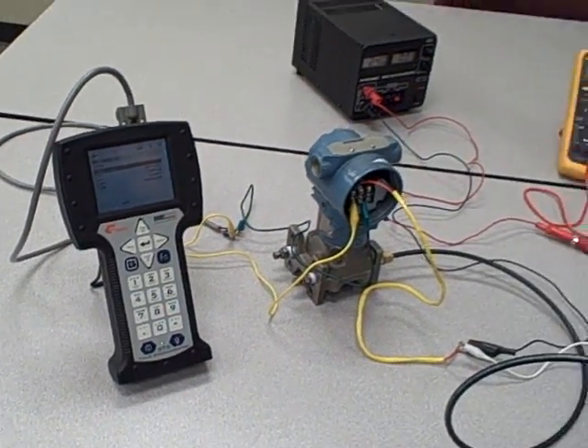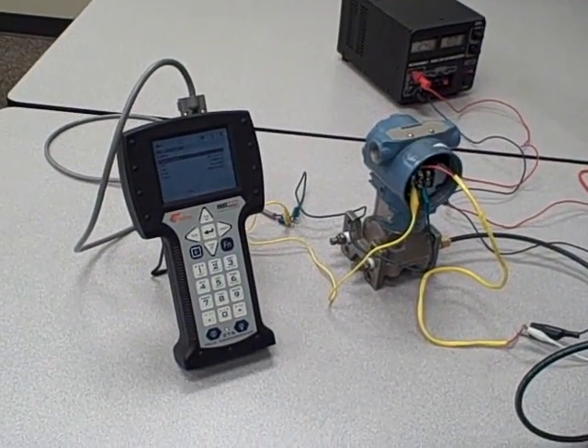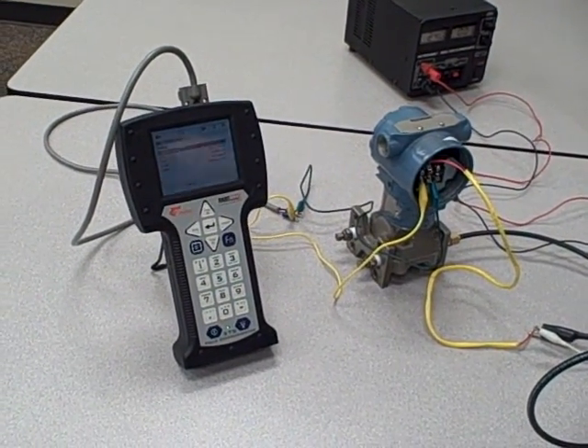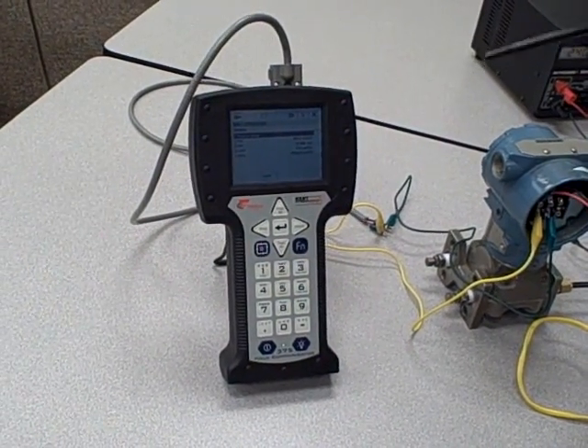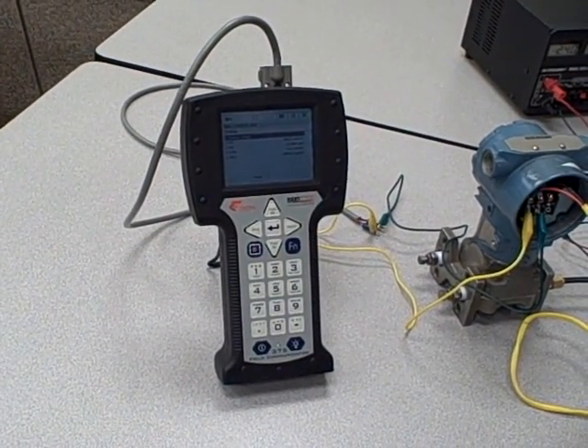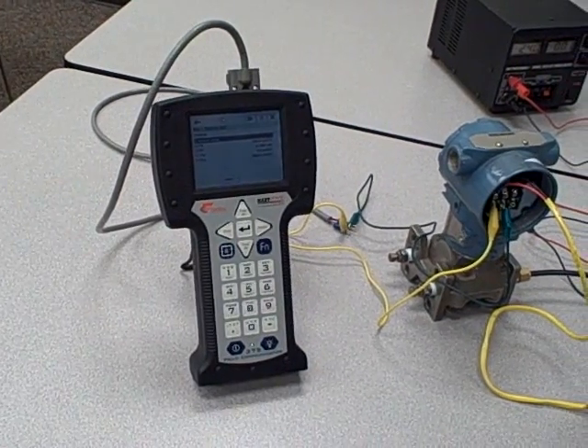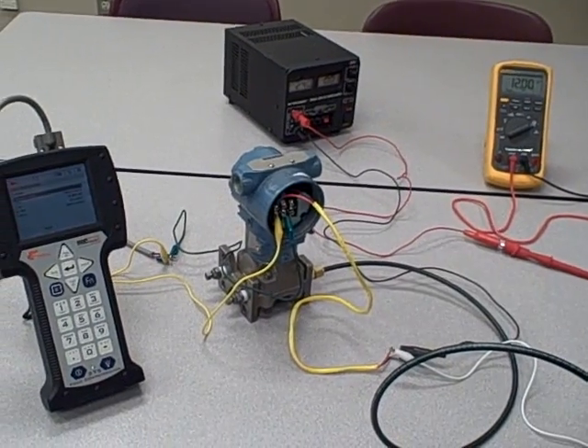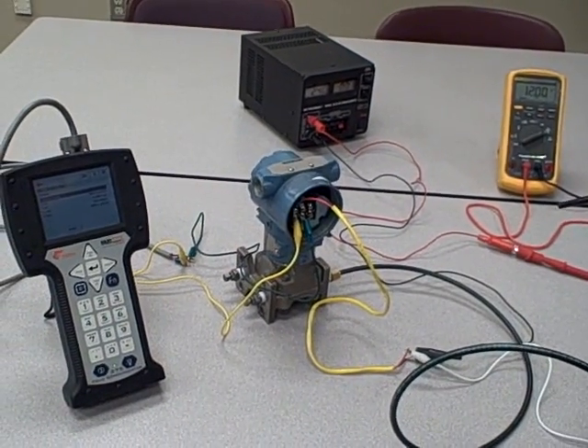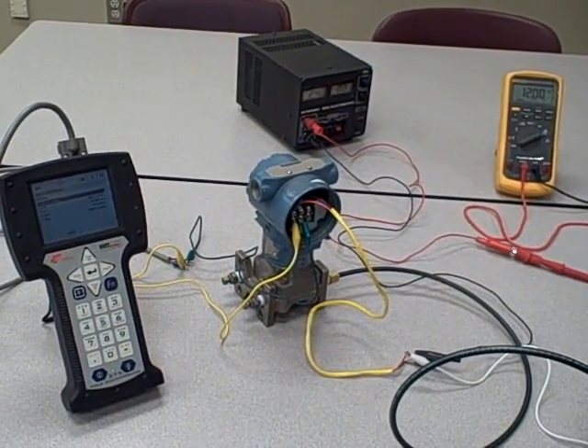So what I'd like to do here is explore in brief how this HART communicator works. HART stands for Highway Addressable Remote Transducer, and it's a digital protocol that was invented to work in superposition with the normal 4 to 20 milliamp DC loop. So the DC 4 to 20 milliamp loop that everyone is familiar with analog transmitters really doesn't change.